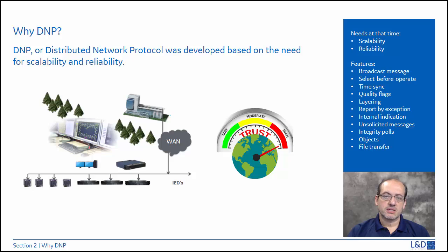So all of these great features, like time syncing, which wasn't a strict thing available in a lot of other devices, and level of support. Devices could be at level 1 DNP or at level 2 DNP. And pay attention to this. DNP version 3 is referred to, sometimes the V is dropped, so we say DNP3, and then the level of support of the device. So you have DNP3-L1, that's a DNP3 device level 1, and DNP3-L2, the DNP3 level 2.